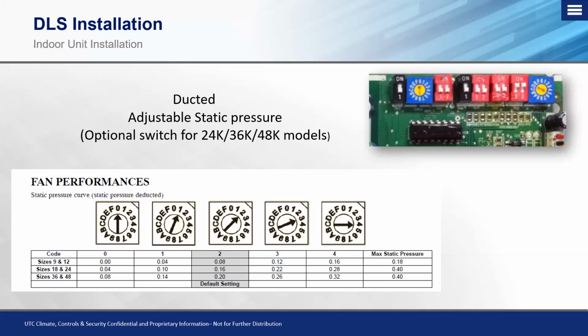Now, if we move up in size to the sizes 18 and 24, you'll see the default setting is 0.16, and the maximum static pressure setting is 0.4 inches of static, which with that, we have a little bit more flexibility on what we can do as far as a couple different takeoffs. But again, these systems aren't designed to have 5 or 6 different takeoffs. Typically about 2 to 3 on average is what we see, and that's more than acceptable.